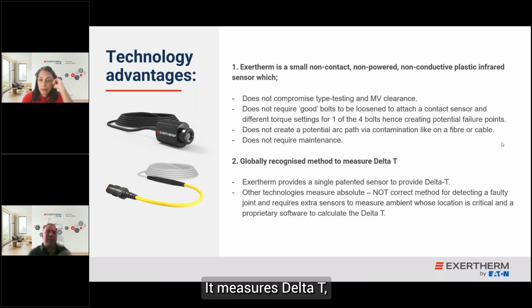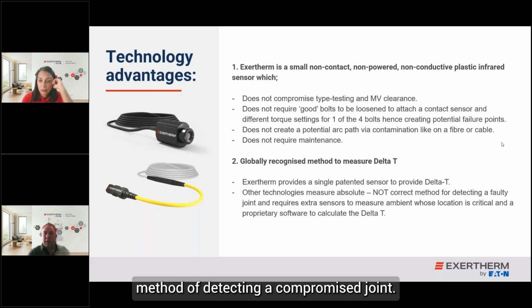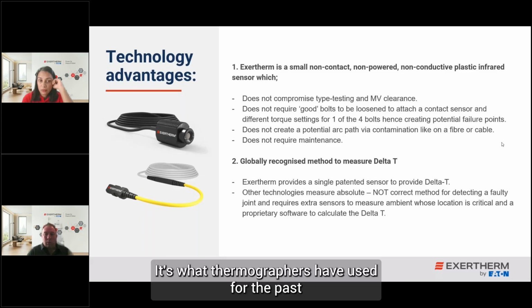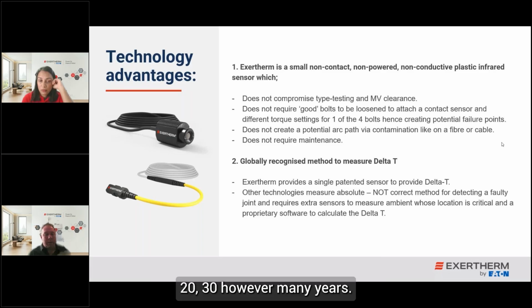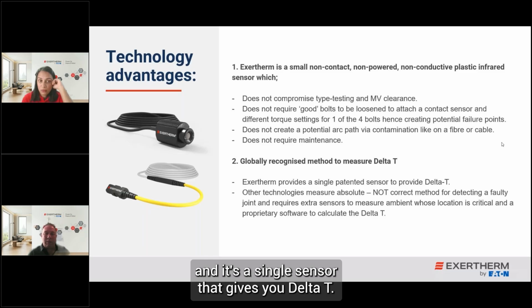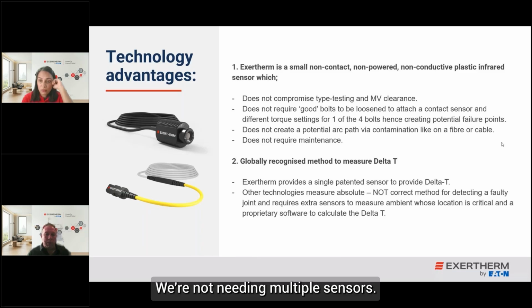It measures delta T, and that's really important - it's that globally recognised method of detecting a compromised joint, what thermographers have used for the past 20, 30, however many years. So it's globally recognised, and it's a single sensor that gives you delta T, we're not needing multiple sensors.